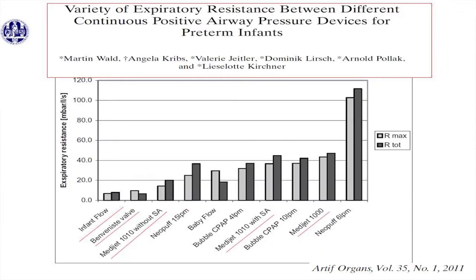But then, this is a bench test. Angela Kribs and Martin Wald did this, with all kinds of CPAP devices. And these are the devices that have the fluidic flip or the jet flow. And you see that there's less resistance in the infant flow driver. And the funny thing is they also used the MediJet without a sound absorber. Because the problem with the infant flow driver is noise, it makes a lot of noise. So they invented a sound absorber. And they didn't test it on the infant flow without the MediJet. You can see that if you use a sound absorber on the expiratory valve tube, it will increase your expiratory resistance. But anyway, it showed that it has less expiratory resistance in a bench test.